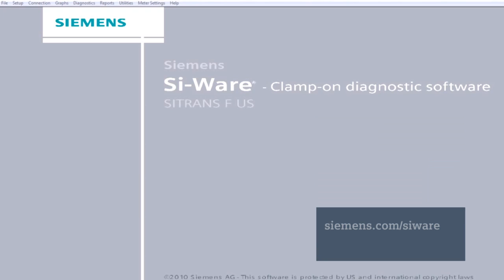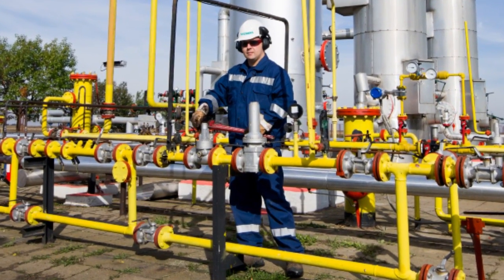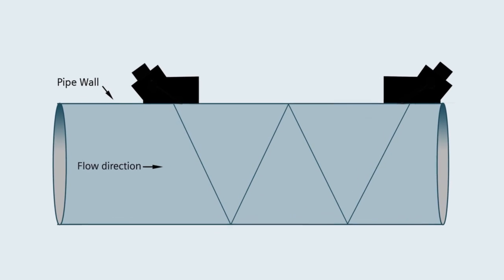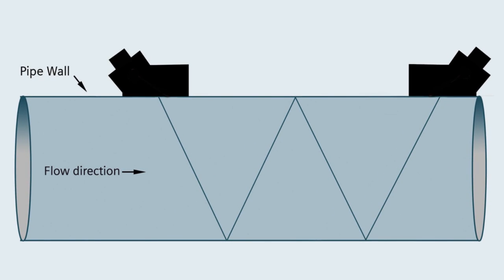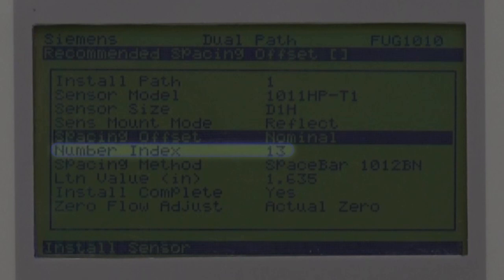The FUG-1010 offers two additional mounting modes known as Reflect 4Pass and Direct 3Pass. Selection of these methods is at the discretion of the end user. The gas tool found in Siemens' free software utility, Si-Ware, will identify applications benefiting from these mounting methods. It is recommended to utilize the Reflect 4Pass method on small pipe sizes 6 inch or less. The increased spacing and double bounce sonic transmission method provide increased flow stream averaging and improved noise immunity on these smaller pipe sizes. Once you've selected a mounting mode, the FUG-1010 will calculate the required sensor spacing based on all your program entries. Note this number for use as you mount the sensors.